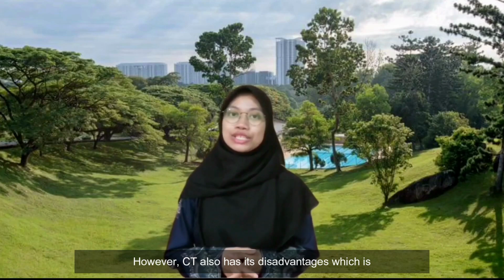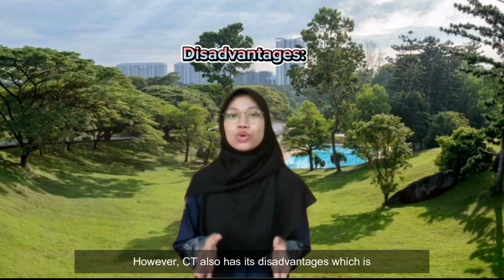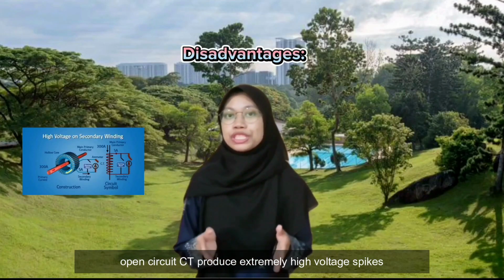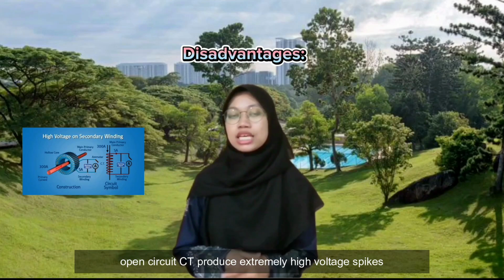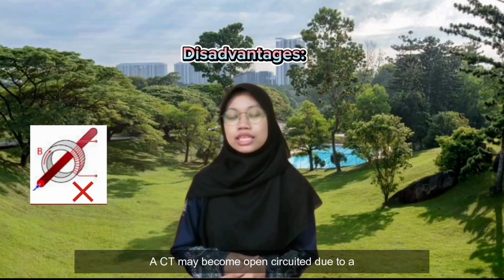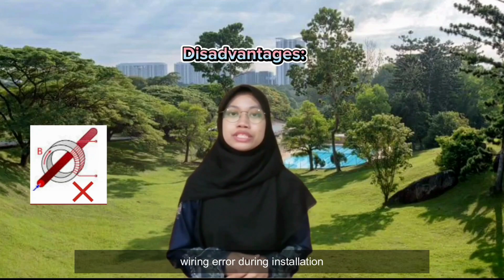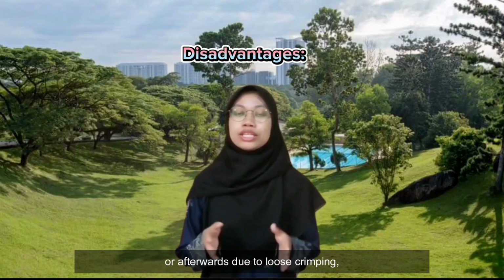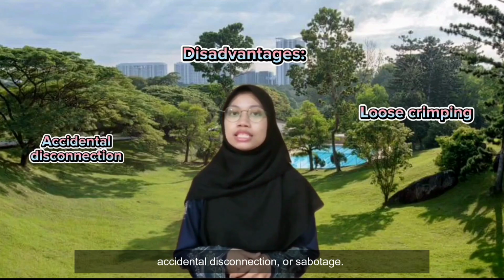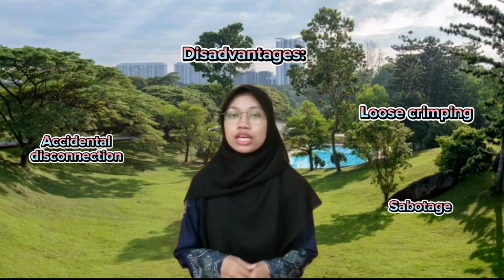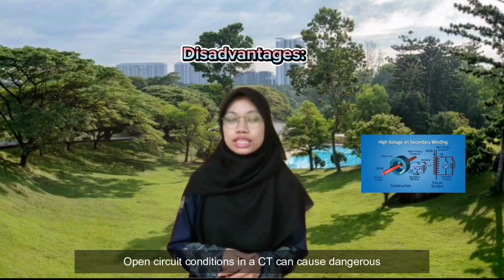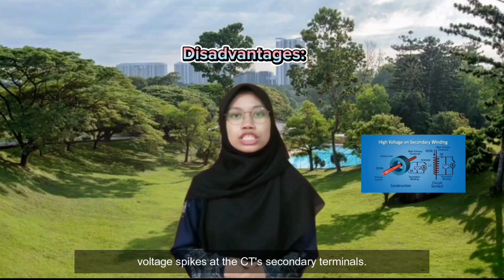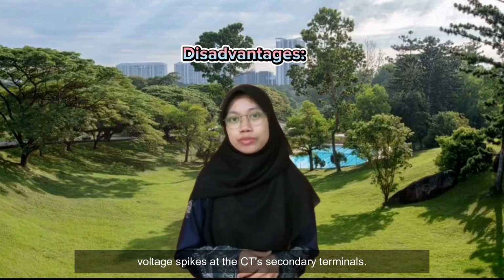However, CT also has its disadvantages, which is that an open circuit CT produces extremely high voltage spikes. A CT may become open circuit due to a wiring error during installation or afterwards due to loose crimping, accidental disconnection or sabotage. Open circuit conditions in a CT can cause dangerous voltage spikes at the CT secondary terminals.